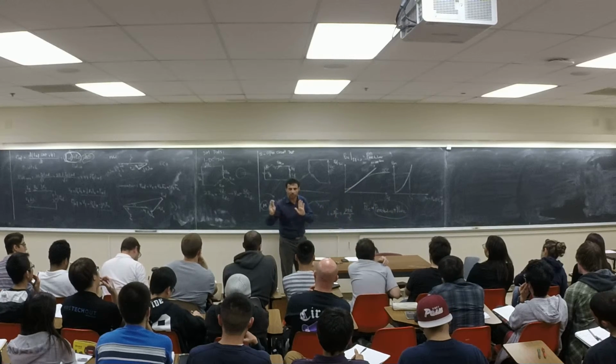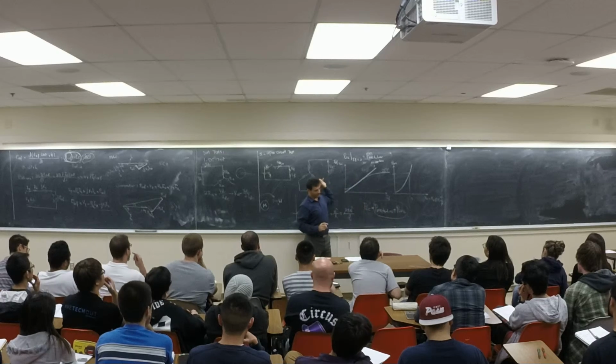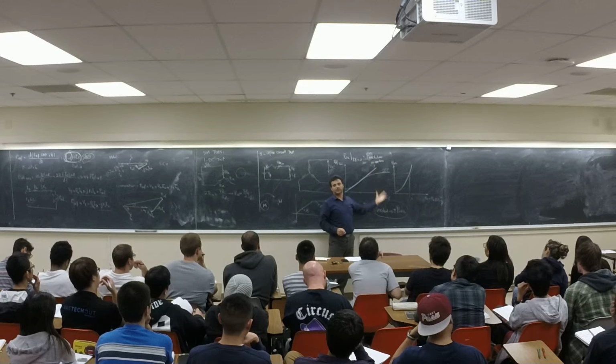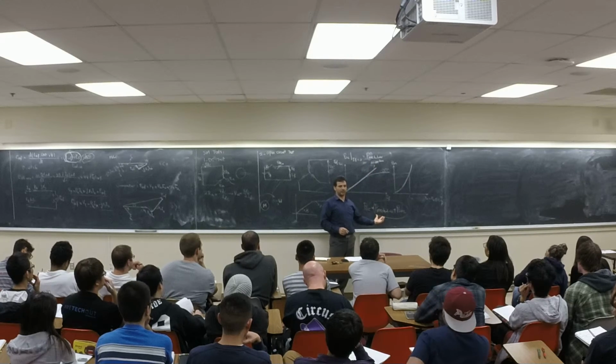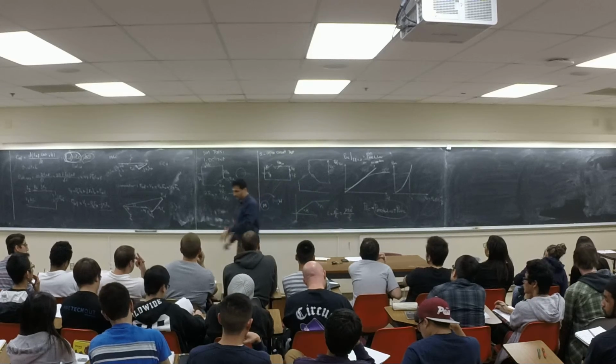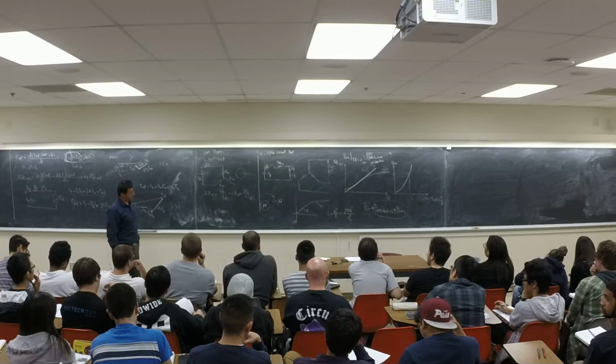But if you still want to separate them, how much is the core loss and how much is the mechanical loss, you can open the excitation system and measure the loss. This one is going to be the mechanical portion of that. This is because of friction, windage loss, and those kinds of things. You can measure them separately. Now we did the open circuit test.